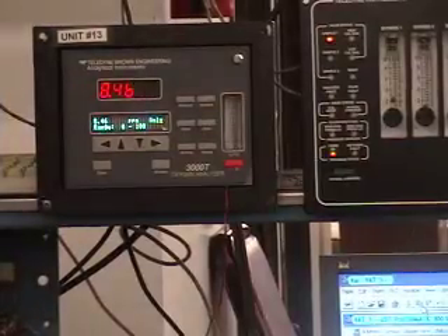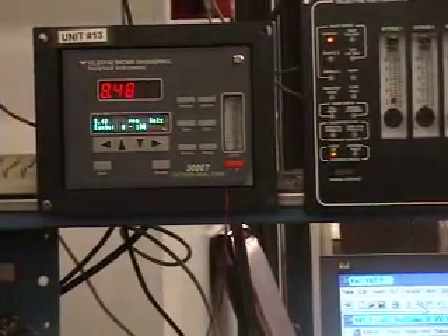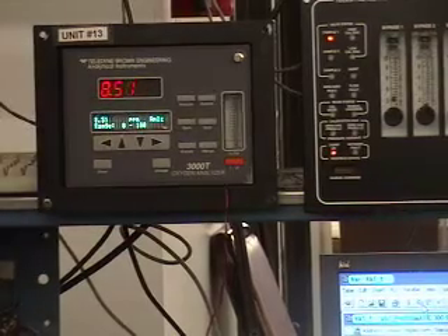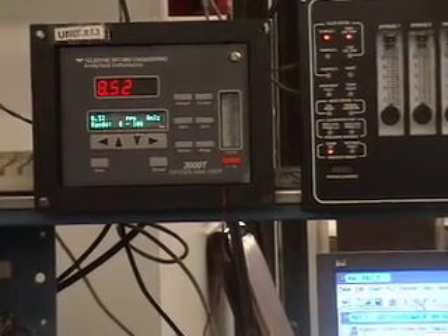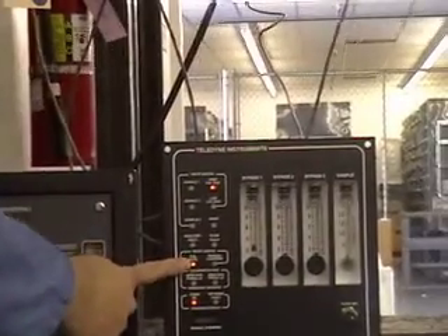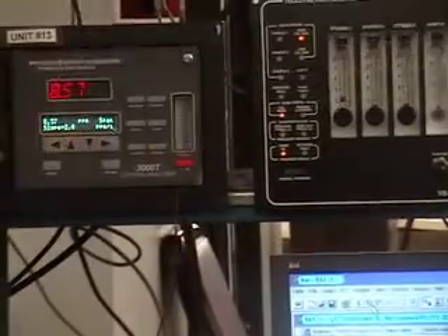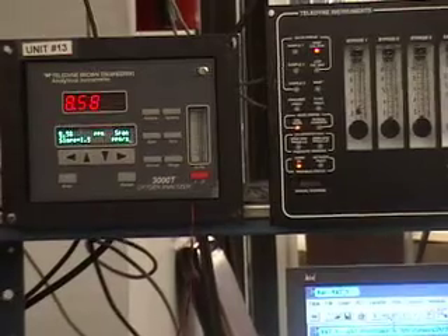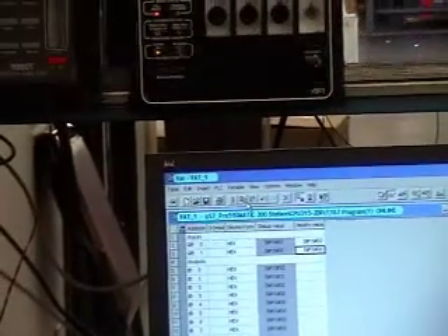All right. So it's reading close to 8 ppm, but not quite 8 ppm. So I'm going to send a command now, one step first. And you can see that it went to the high cal mode, the analyzer detected in the span mode, and then I'm going to tell it to return to valve 2. So when it is done, it will return to valve 2.